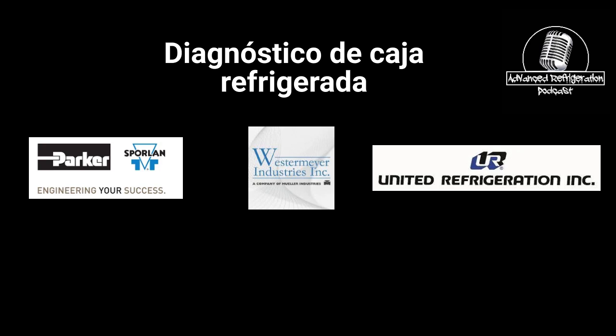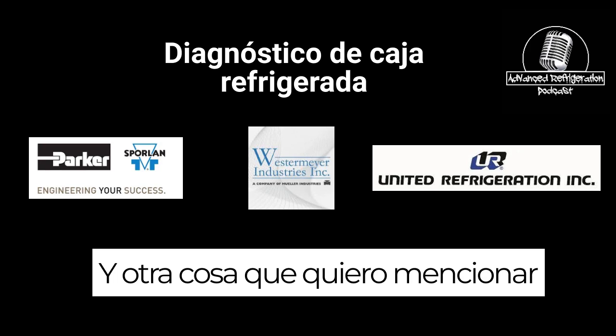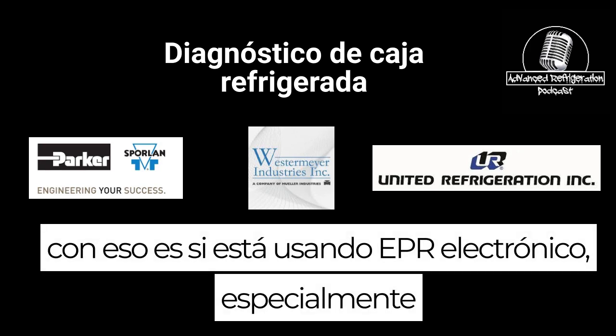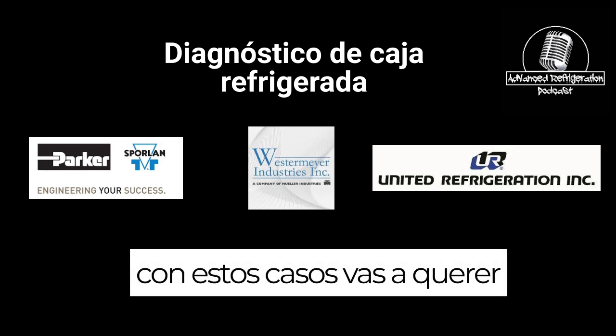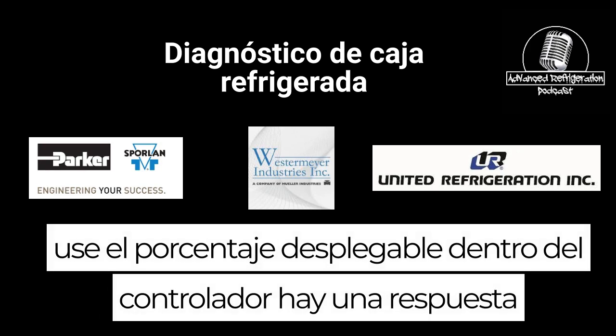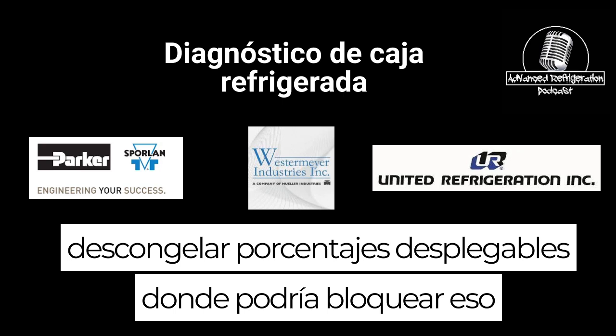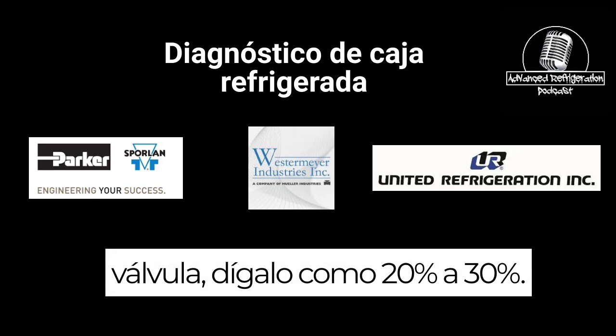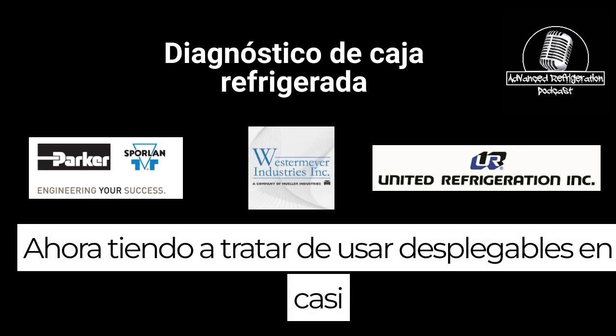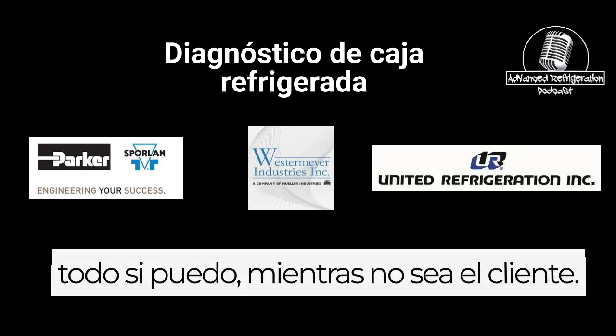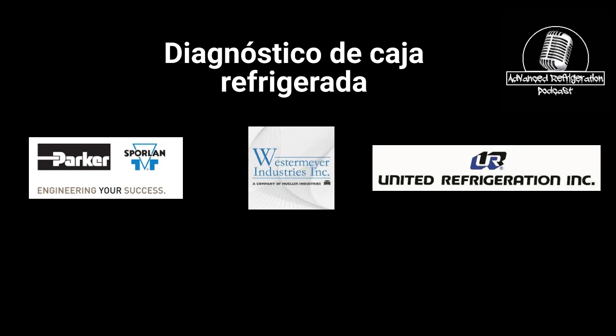And one other thing I want to bring up with that is if you're using electronic EPR, especially with these new cases, you're going to be wanting to use pull down percent. Inside the controller, there's after defrost pull down percentages where you could lock that valve, say at like 20 to 30%. Now, I tend to try to use pull downs in just about everything if I can, as long as it's not the customer specific view.